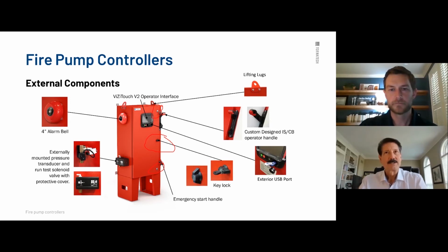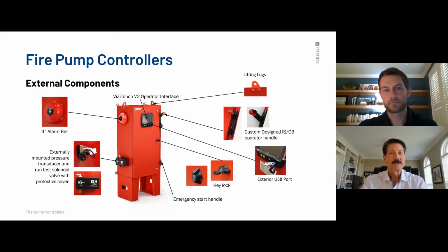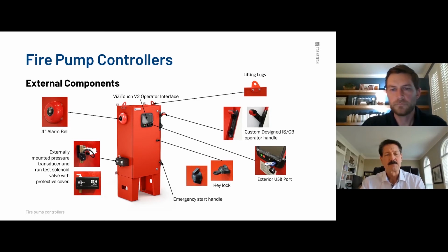I'd like to add a couple things. The keys, as Cole said, if you open the door, they're on the bottom left side. They're tie wrapped to the inside of the enclosure. So someone calls, say, hey, I need keys, they didn't come. It's very highly unlikely. Number 2 is these legs, size-wise. These are 12 inches, because code requires 12 inches from finished floor to your first termination of power, the first entry to a power device. And you don't necessarily need those legs because you can wall mount this, which obviously makes it quite nice. But I just wanted to point that out because it does make a big difference.